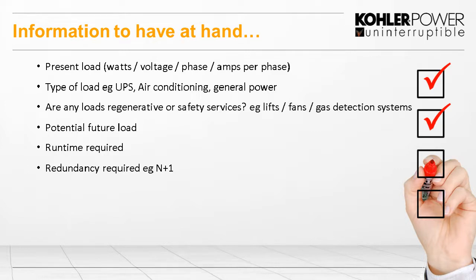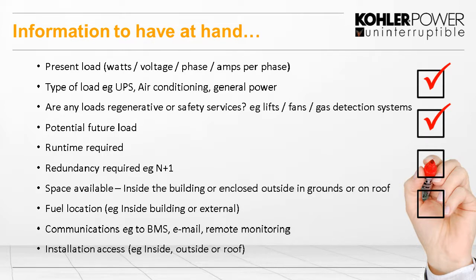Once we know that, we want to know how long we need to keep this set running for. Can we put refueling in, or do we need to put the tanks in required for the runtime that the customer requires? And also, does the customer want redundancy here? Like UPSs, we can add redundancy in by paralleling generators to have N+1 capability in case of a failure of a set, so that we still have another one available. So once we know all that, we'll understand the space requirements, and we need to understand what's available. So is it going to go inside a building, outside in an enclosure, or is it going to go on a roof, for example? So then we will work out where the fuel goes, inside or outside, located depending on the runtime, actually in a container with the set, or is it in a remote fuel location?